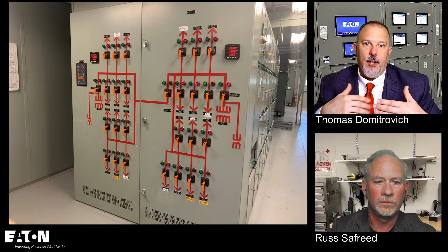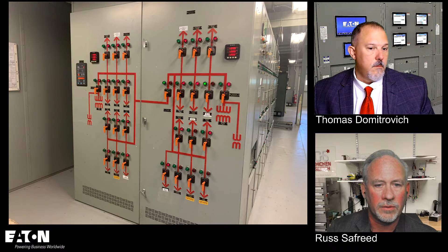So this is another way to get outside the arc flash boundary. This is a facility I used to work at. We were big, probably back in the 90s, on putting mimic panels on the end of the switchgear, or elsewhere in the room, or even outside in a cabinet. You can install the pistol grip switches at the end instead of in the front of the switchgear. In this example, there are no switches in the front, so this is a true engineering control situation. There's no way the guy can bypass an administrative control and operate that breaker. He's got to come down here to the end.